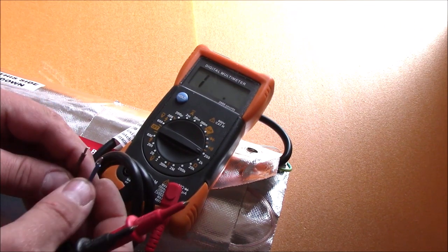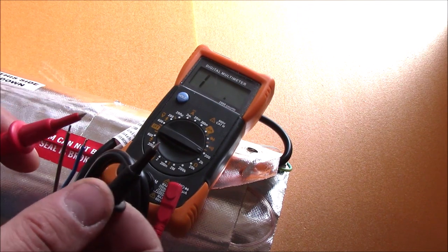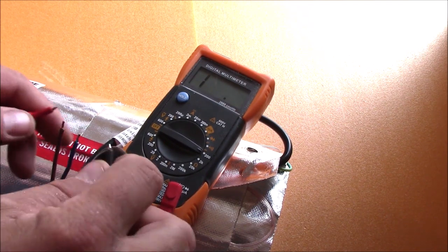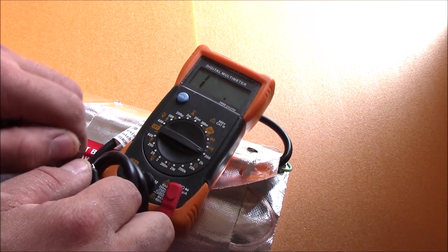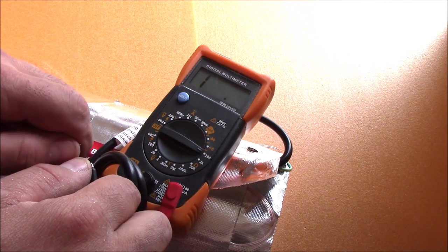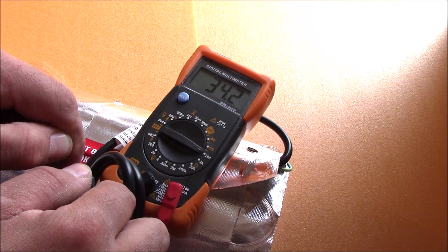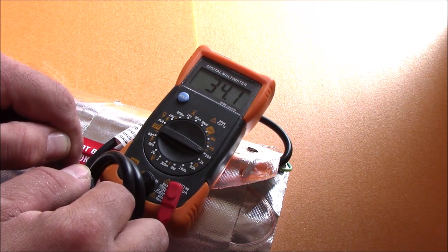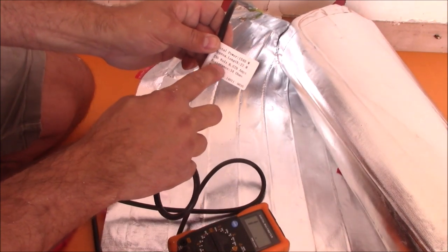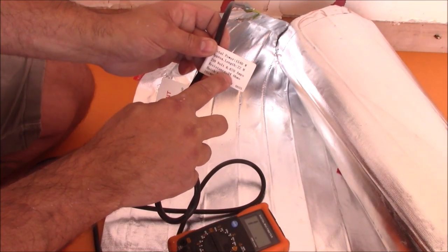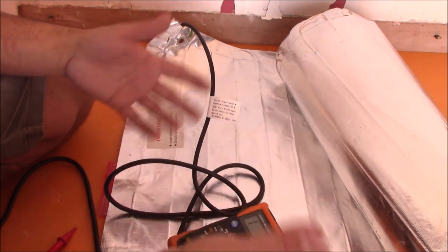So then we need to test these two wires, the blue one and the brown one. You take the two probes from the multimeter, stick it onto the wires at the end, and the multimeter should show the resistance. So 34.1 ohms. That's the resistance you can check on the mat - it should be 34 ohms. So it's very similar. I'm sure that the mat is not damaged, so I can lay it.